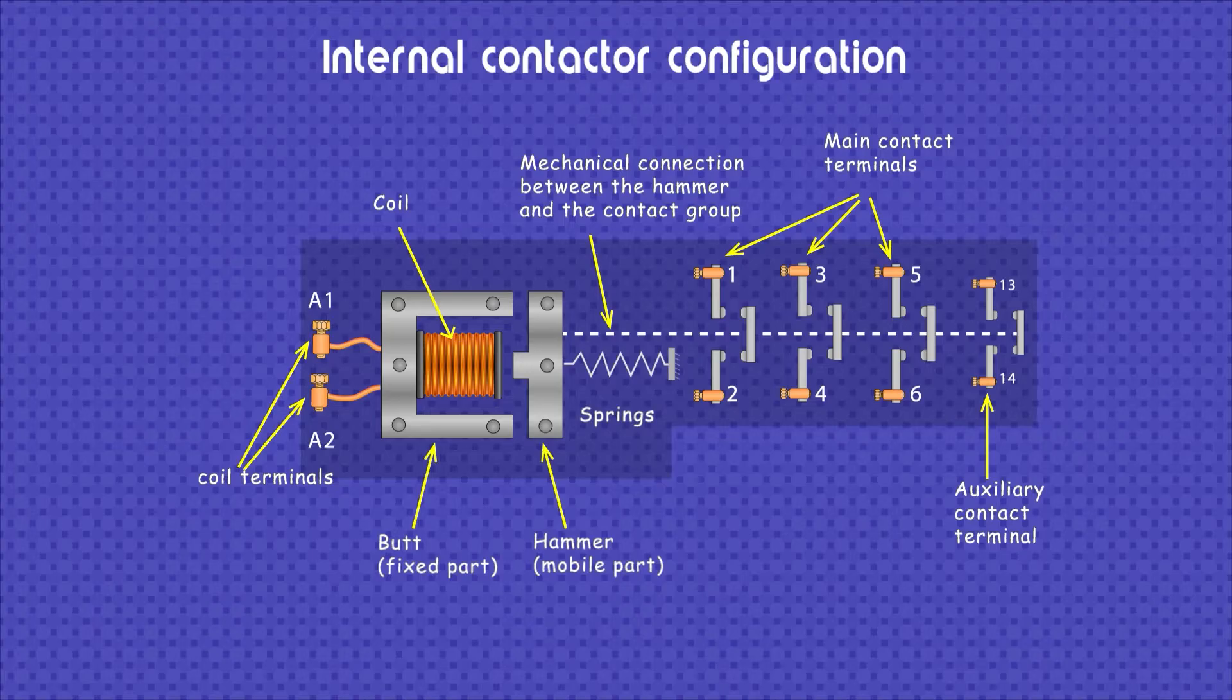The mechanical connection is the rigid element that joins the contacts to the moving part, here it is specified with dotted lines. The spring is the element that allows the butt to be separated from the hammer when the coil is de-energized. On the left side we have the terminals that connect to the coil and on the other side we have the main and auxiliary contacts of the contactor.